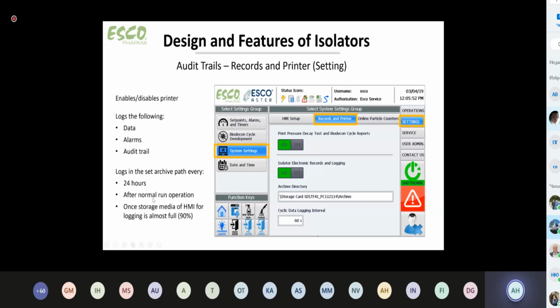There's this here. You can see that in this case, there will be on to allow you to print out the pressure decay and biodecon cycle report. You can have electronic records and logging. That's on. You can turn it off if you want to. You can save all of these files in a certain directory. In this case, there's an SD card, so it's a local storage card. You can transfer it directly to a computer or something else, and this will be the logging interval. This is actually 1 minute. 1 minute is very, very common that we have this here.